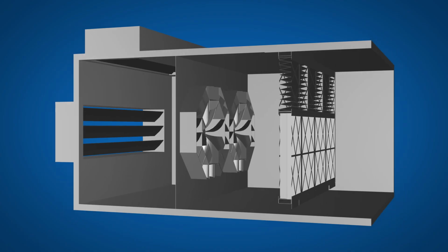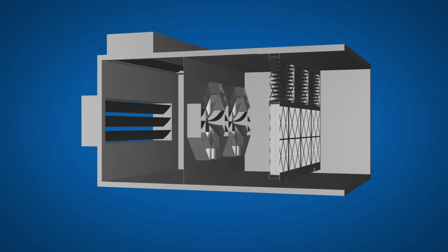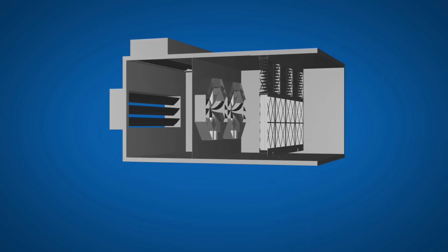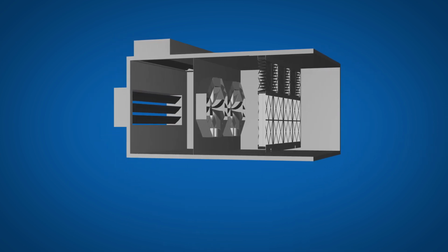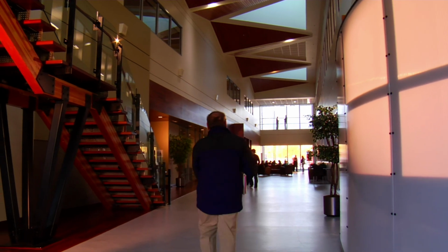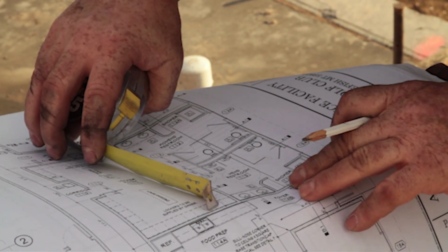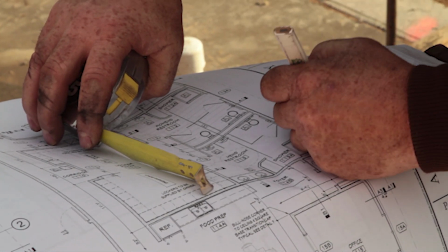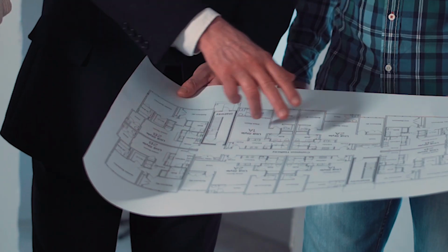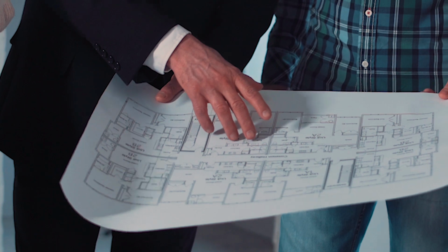For many years, HVAC designers have specified static mixers to reduce the impacts of temperature stratification. Although these devices are effective, they require additional tunnel length in the air handling unit. This leaves the designer with a design dilemma. They know freeze protection is a critical requirement in many applications, but they often don't have enough space in the mechanical room to use static mixing sections.